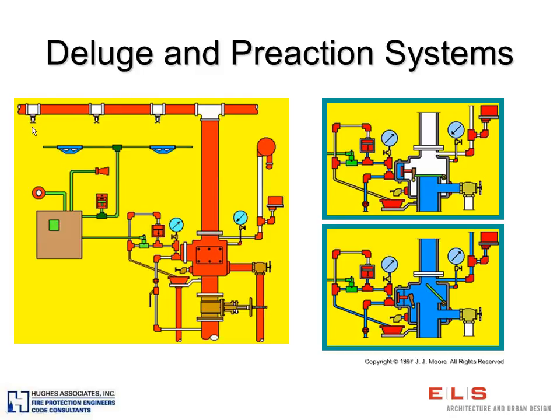But if only this sprinkler opened, you would only get water out of this sprinkler. These two would remain closed, and you would not get any water out of them. That's a pre-action system, very common application for cultural preservation.